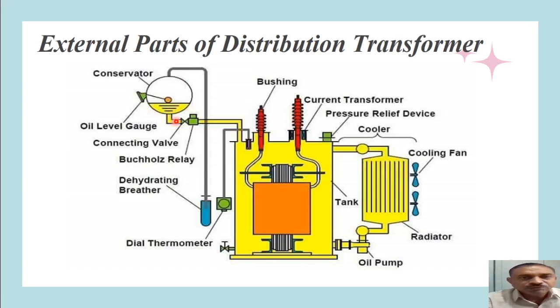This protects the oil from dielectric failure. When oil passes from the main tank to the conservator, a Buchholz relay is fixed in the pipe. The Buchholz relay operates on a float mechanism — whenever oil expands and gases develop, it detects these and operates a mercury switch, triggering an alarm to indicate that a fault is occurring inside the transformer, as oil is expanding at a faster rate.